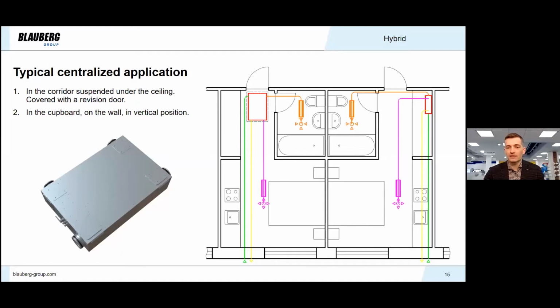In this case, the unit is located between the false ceiling and the concrete overlap between floors. The maintenance can be done through the revision door in the false ceiling. It is available as an accessory and developed strictly for this unit. I mean, the dimensions of the revision door correspond to the dimensions of the unit.